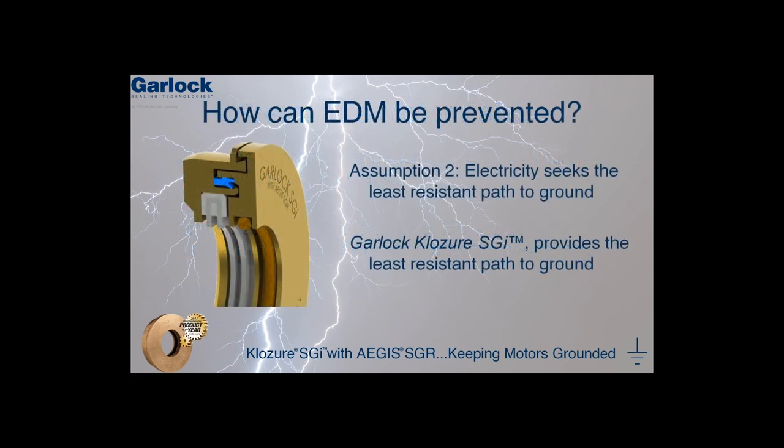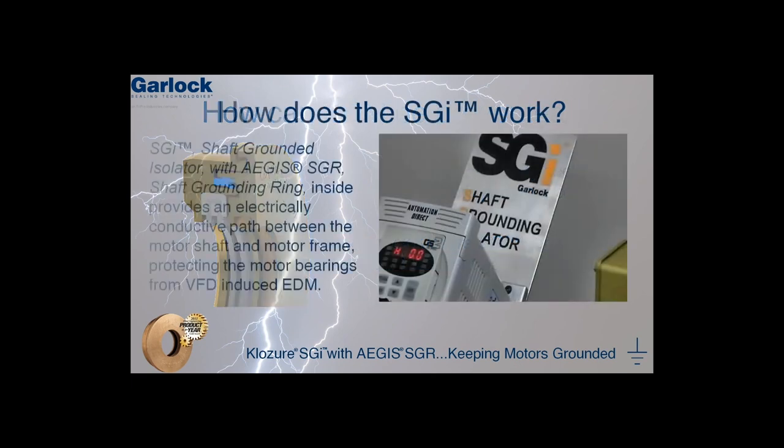So how can EDM be prevented? Based on Assumption 2 that electricity seeks the path of least resistance to ground, we can use the Garlock Klozure SGi to do so. The Klozure Shaft Grounded Isolator uses the Aegis shaft grounding ring in conjunction with the Klozure Guardian Bearing Isolator. In order to protect the motor bearings from VFD induced EDM, we can use the SGI to provide an electrically conductive path between the motor shaft and the motor frame.